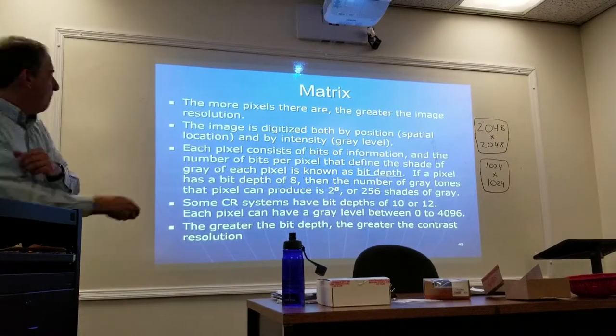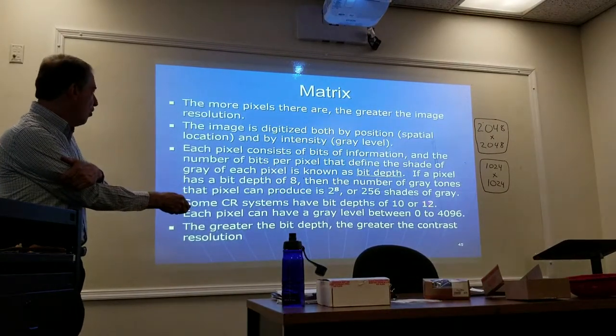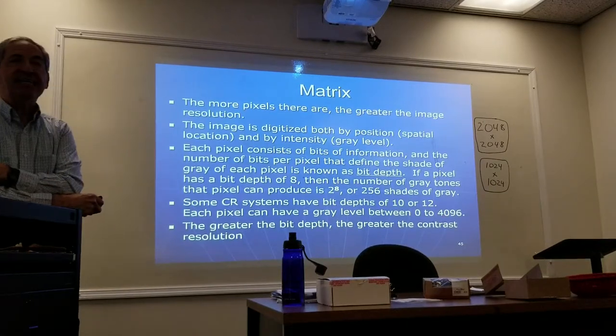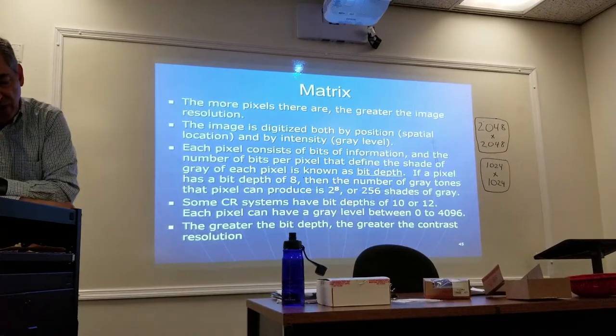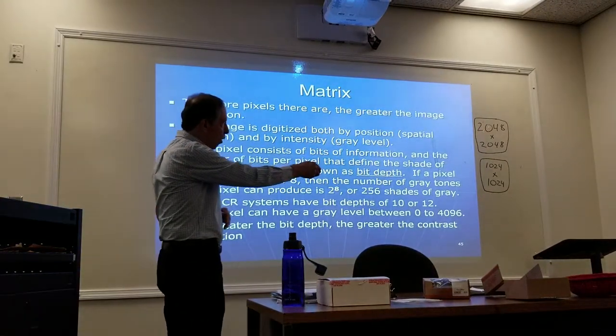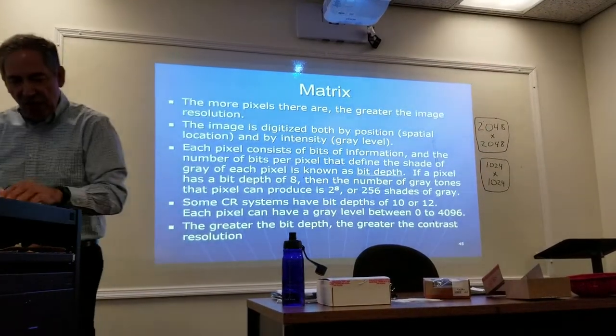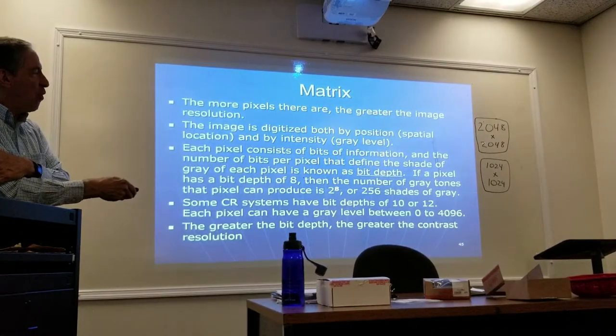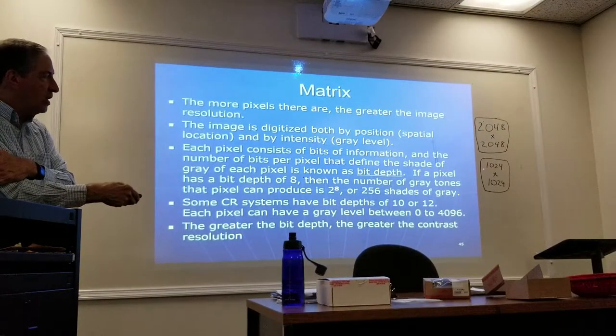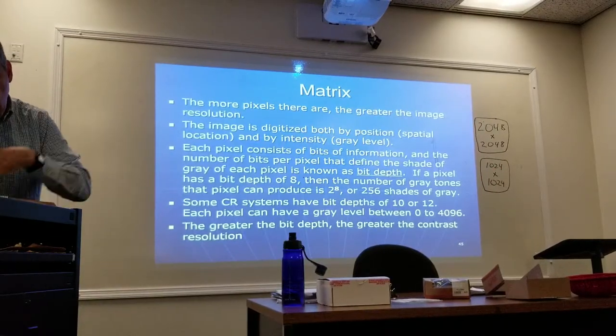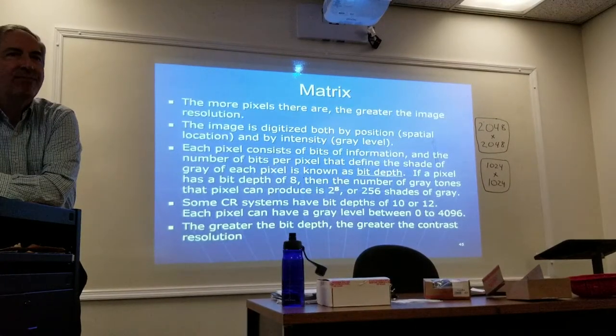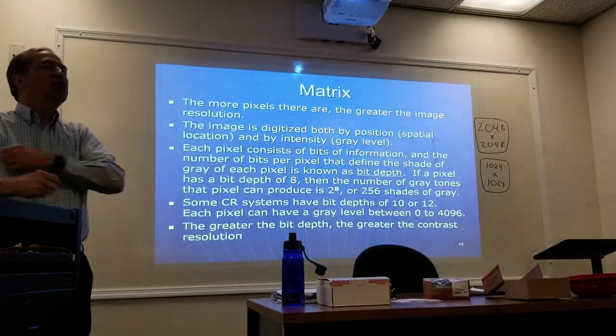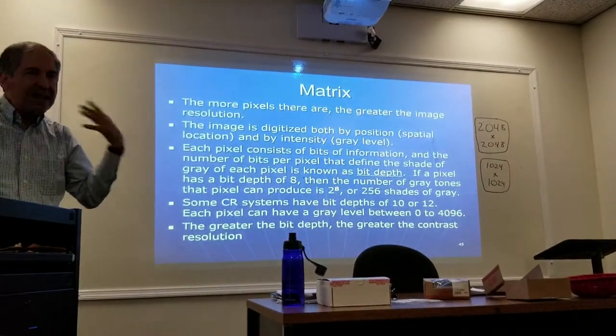Some CR systems have a bit depth of 10 or 12 — that means 2 to the 10th or 2 to the 12th. The greater the pixel depth, the greater the contrast resolution. 2 to the 12th represents 4096 shades of gray. The greater the image matrix size, the greater the spatial resolution. For example, a matrix of 2048 by 2048 has better spatial resolution than 1024 by 1024.